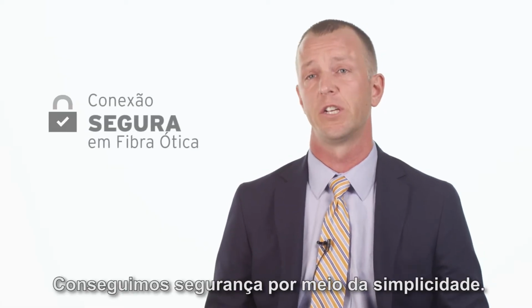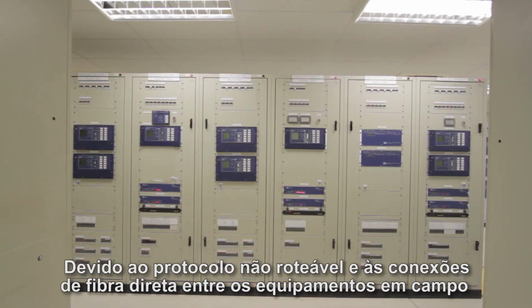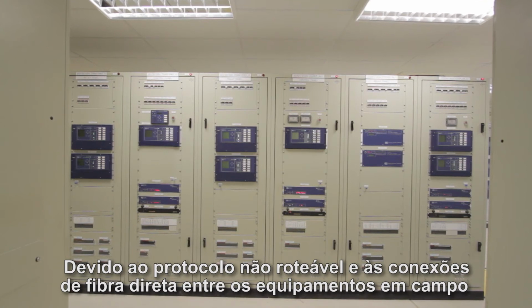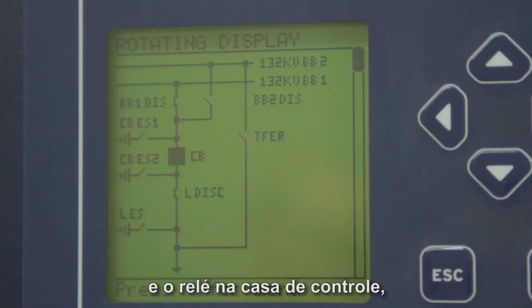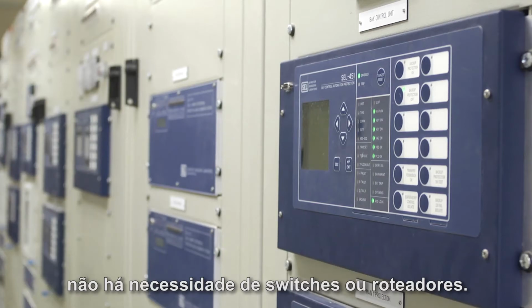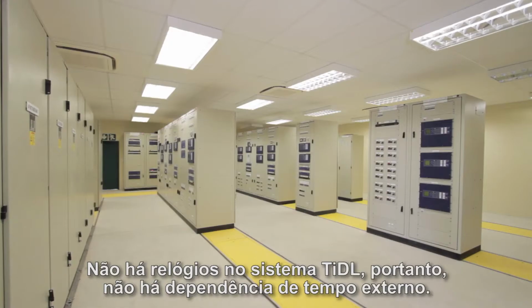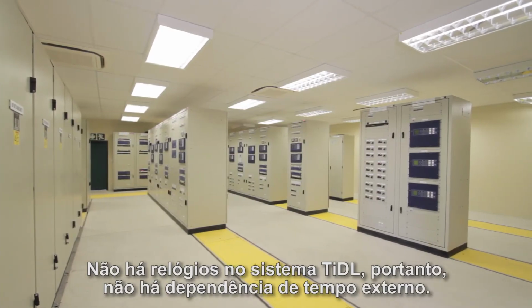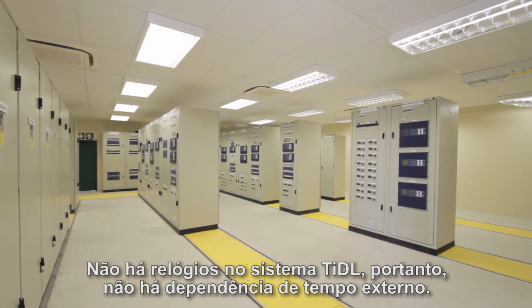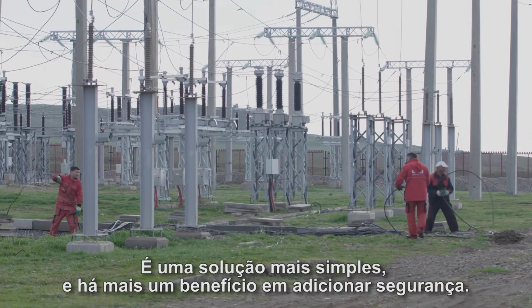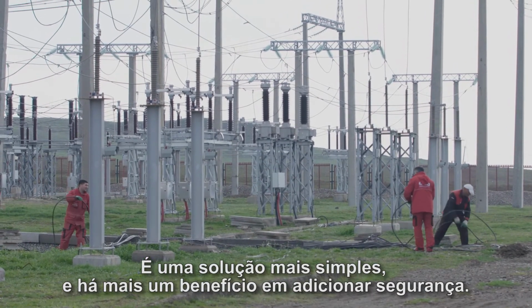We achieve security through simplicity. Because of the non-routable protocol and the direct fiber connections between field modules and the relay in the control house, there's no need for switches or routers. There are no clocks in the TiDL system, so there's no reliance on external time. It's a simpler solution, and then there's the other benefit of adding safety to that.